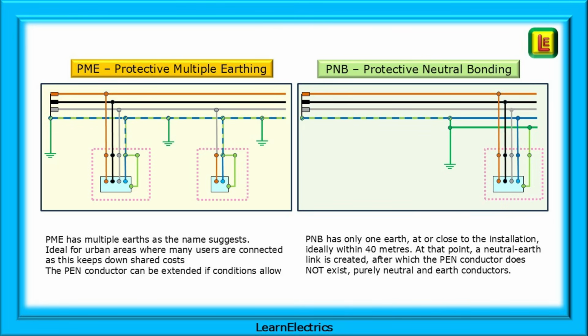Ideal for urban areas where many users are connected, as this keeps down shared costs. The PEN conductor can be extended if conditions allow. PNB has only one earth at or close to the installation, as we said, ideally within 40 metres. At that point, a neutral earth link is created, after which the PEN conductor does not exist, purely neutral and earth conductors.